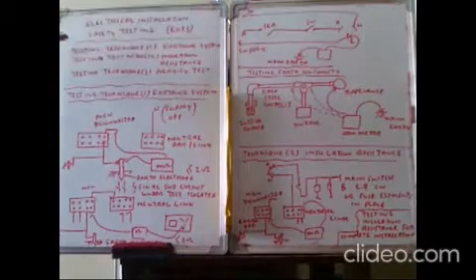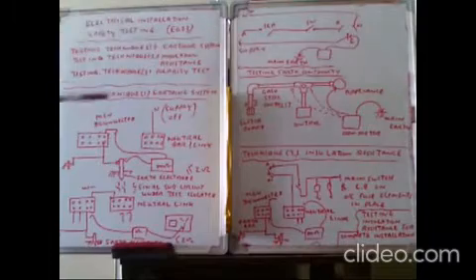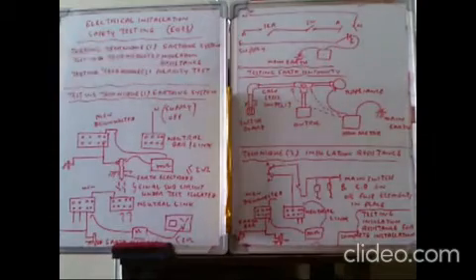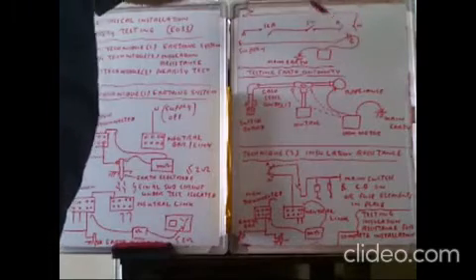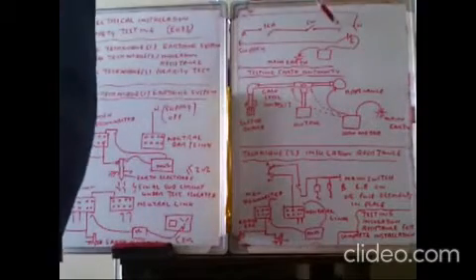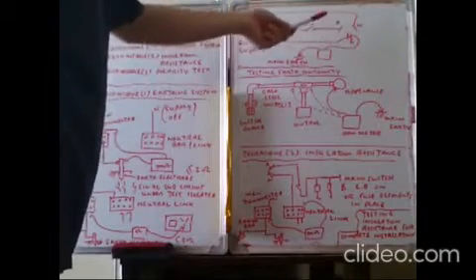The earthing system (MEN system) must be tested. The insulation resistance between the active conductor and neutral conductor, and between the active conductor and earth, must be tested. For polarity testing: the active wire must be connected to the switch, the left side of a socket is active, and the right side is neutral. The active and neutral must not be reversed.